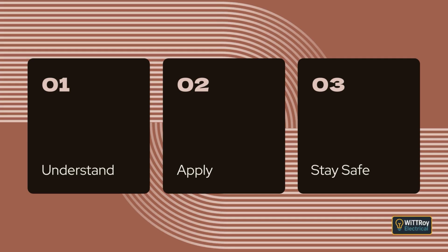The clause also explains that when a standard does not specify a WS classification, the wiring system must be one that can keep supplying the equipment when exposed to fire or when exposed to mechanical damage, or when protected from these hazards by suitable enclosure or by installation in a place where the wiring is not likely to be damaged. The clause includes an exception stating that the fire and mechanical protection requirements do not need to apply when wiring systems are in an enclosure or location that gives the required protection, such as underground cable ducts, concrete or masonry walls or floors, or other fire-rated enclosures with suitable mechanical protection.